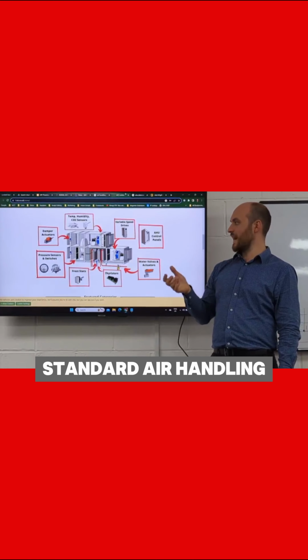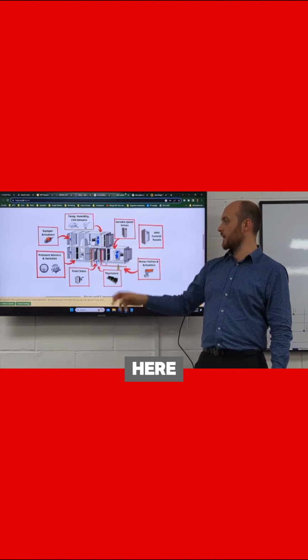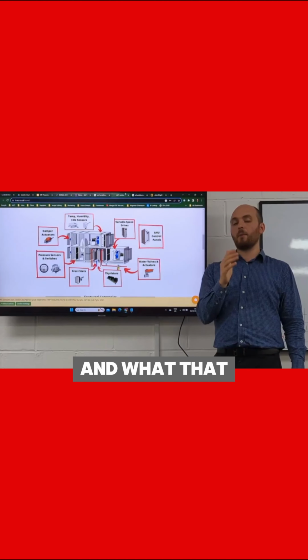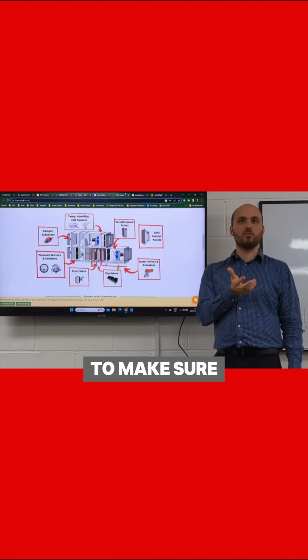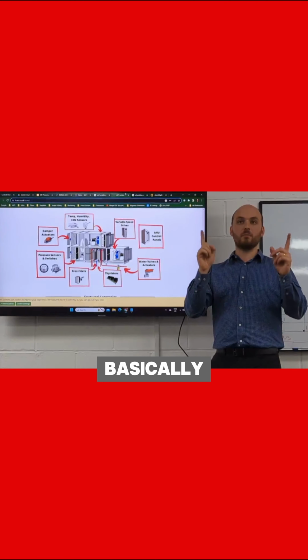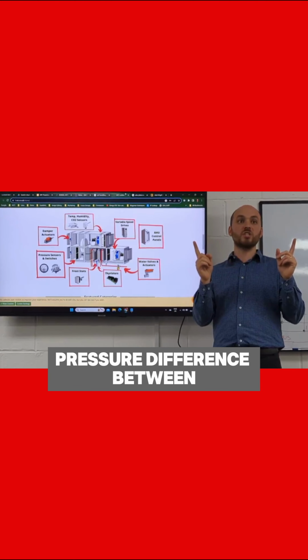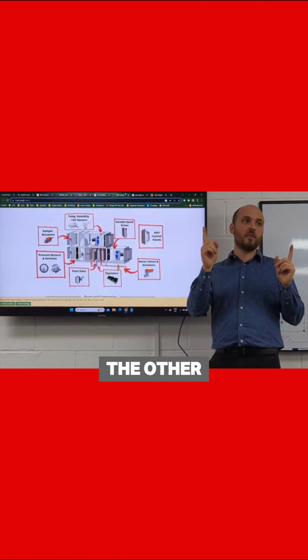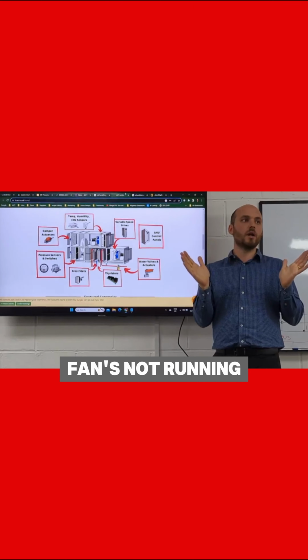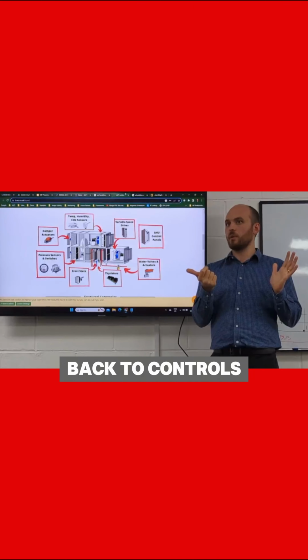With a standard air handling unit, we have a fan, which is this blue thing here, and we provide a pressure switch. What that does is act as a safety function to make sure the fan's running, basically checking there's a certain pressure difference between one side of the fan and the other. If it reads there isn't, it's saying the fan's not running. That acts as an easy alarm signal back to the controls.